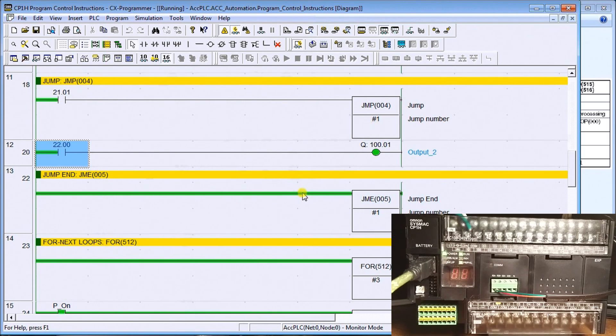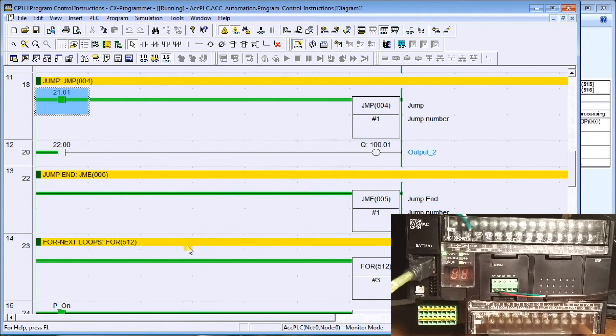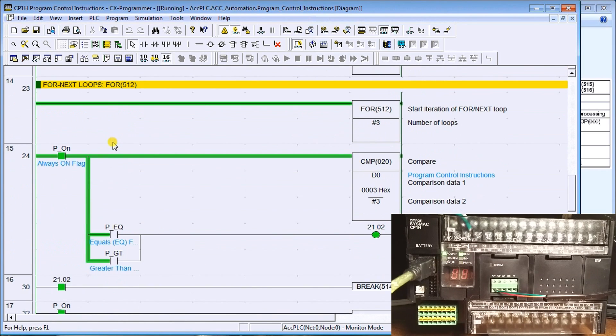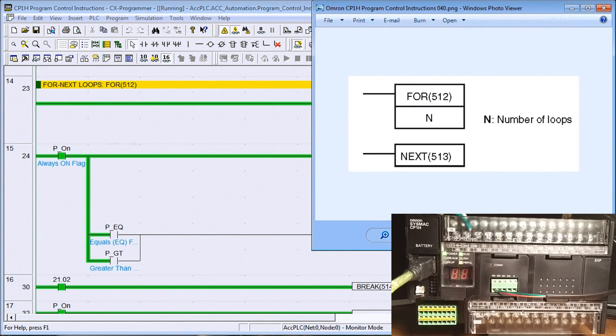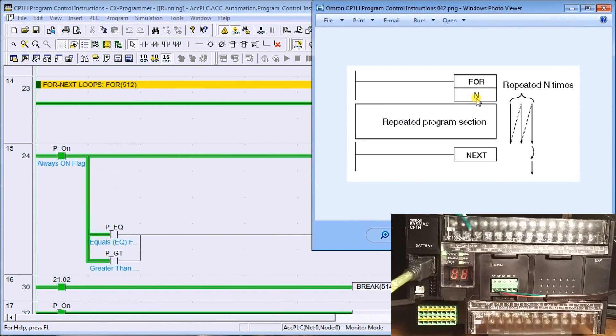So that's the jump statement. We can turn that back on, it'll scan it, and then set it back off again — which is exactly what it did. Our next instruction is kind of unique: it's a for-next loop. What it does is go through the loop a number of times before it returns the scan, so within one scan we can do several different loops and then continue. If we set for three, as the program scans it'll scan that section three times and then continue on.